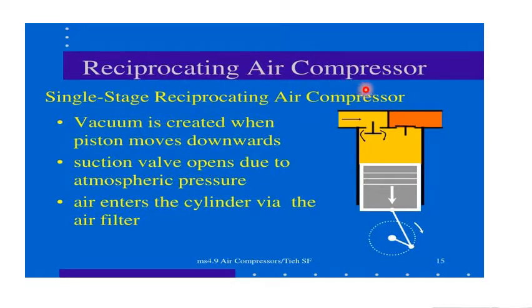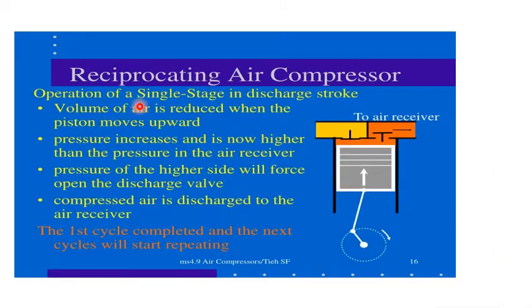In the single-stage reciprocating air compressor, a vacuum is created when the piston moves downward. The suction valve opens due to atmospheric pressure and air enters the cylinder via an air filter. In the discharge stroke, the volume of air is reduced when the piston moves upward, pressure increases and becomes higher than the pressure in the air receiver. This forces open the discharge valve and compressed air is discharged to the air receiver.